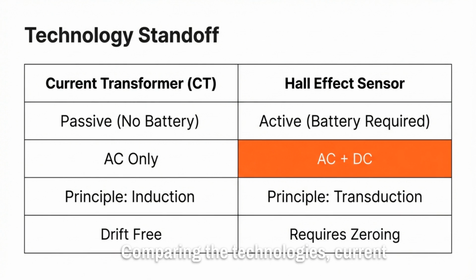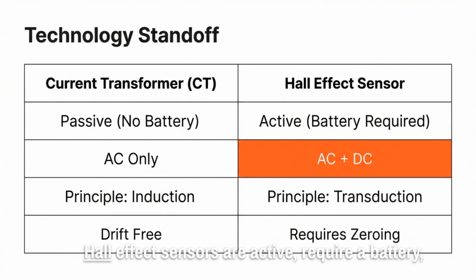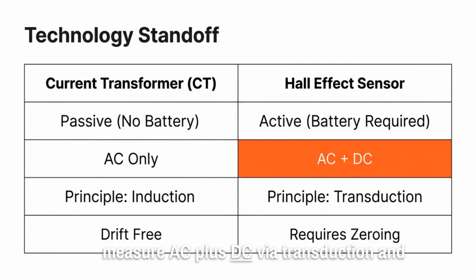Comparing the technologies: current transformers are passive and measure AC only via induction. Hall effect sensors are active, require a battery, measure AC plus DC via transduction, and require zeroing.